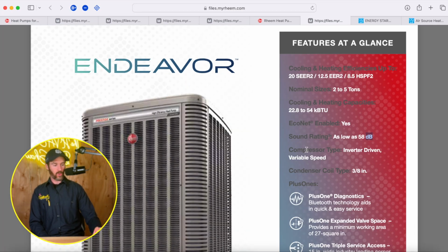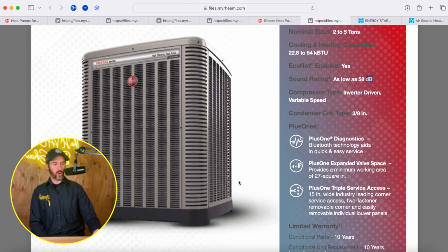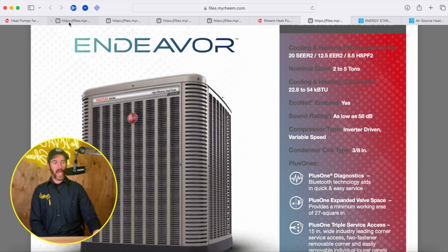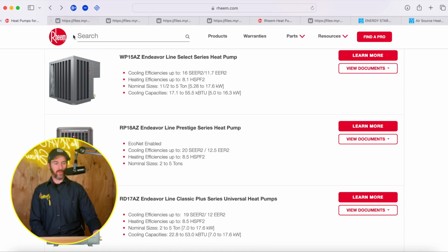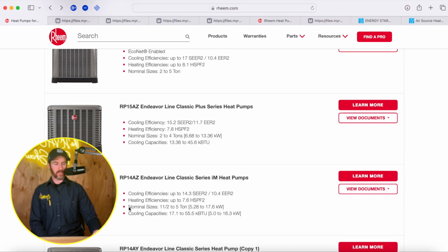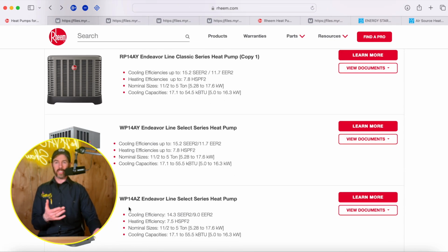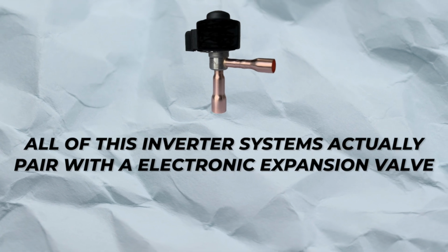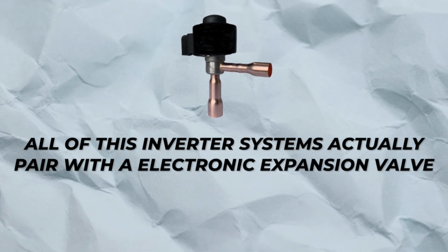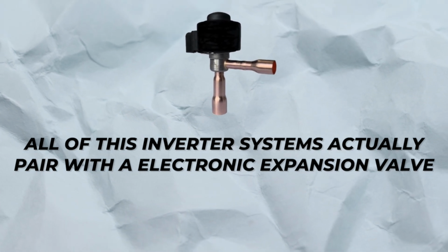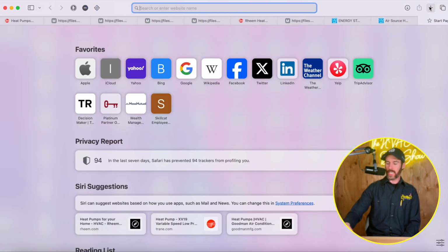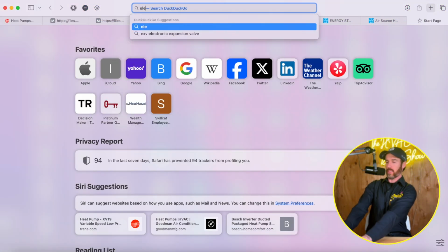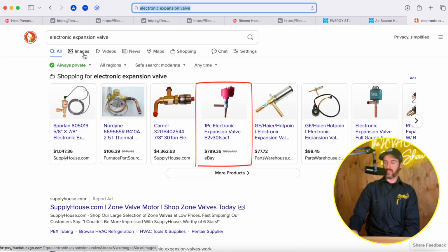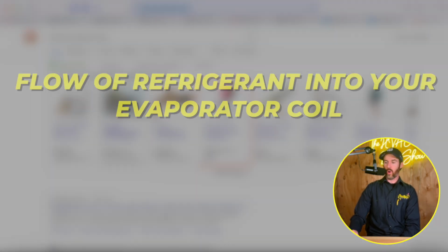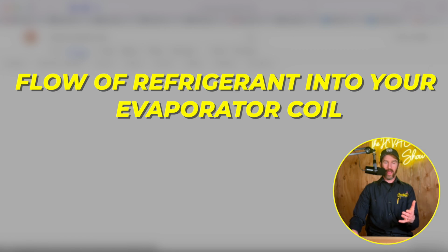It's also an inverter system, and one of the things that you're going to get with these inverters that is a benefit compared to any of the single stage systems we've talked about earlier, or two-stage systems, is that all of these inverter systems actually pair with an electronic expansion valve. Now, if you're not familiar with what an EXV is, I'll pull up an electronic expansion valve so that you can see. But an electronic expansion valve is what controls the flow of refrigerant into your evaporator coil.